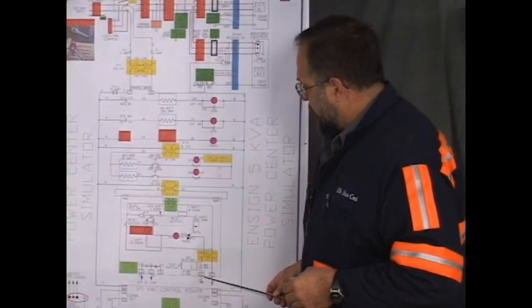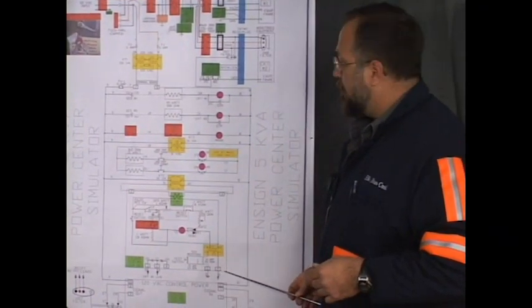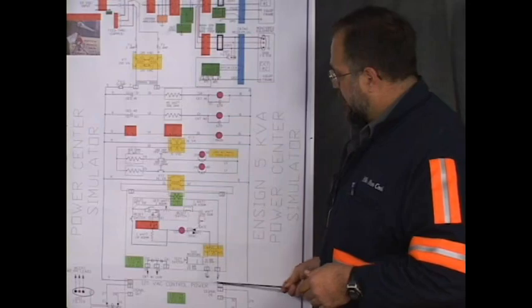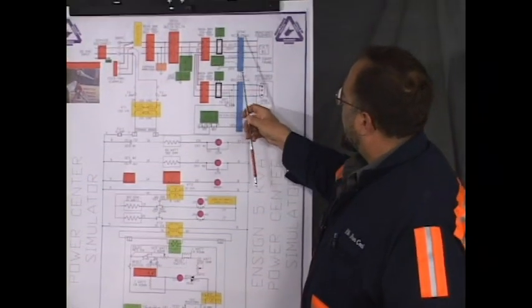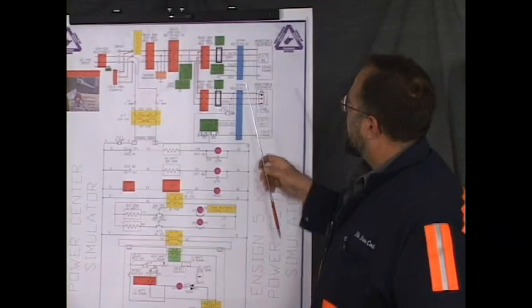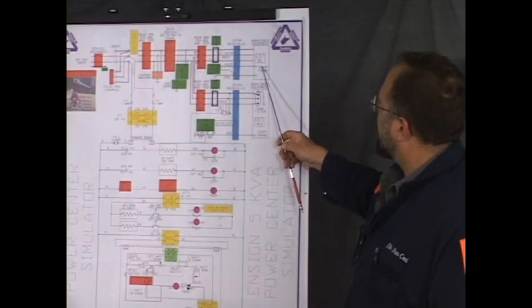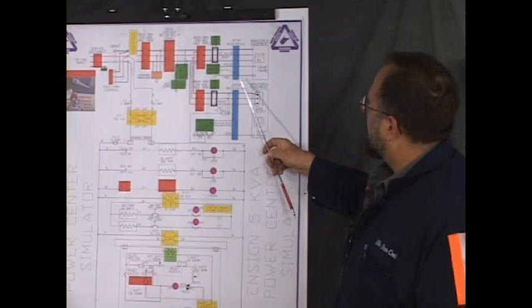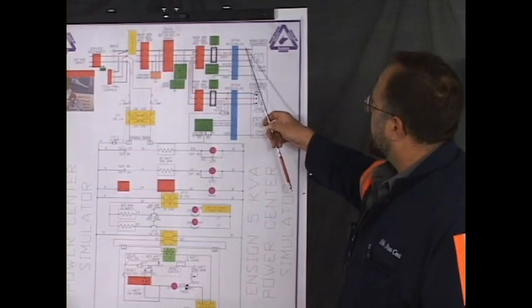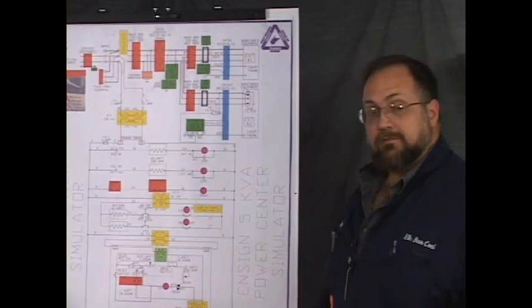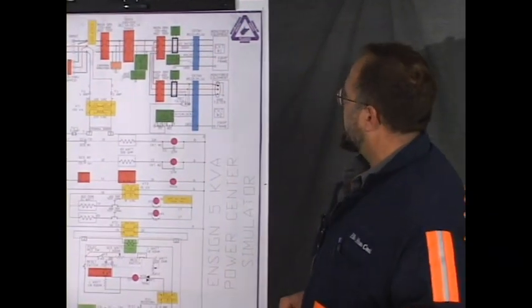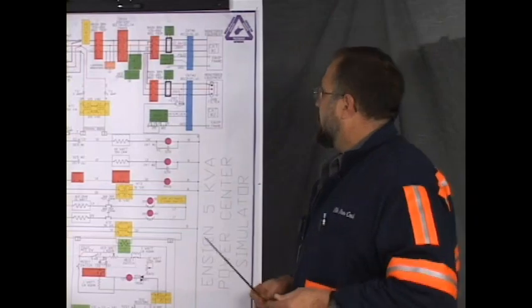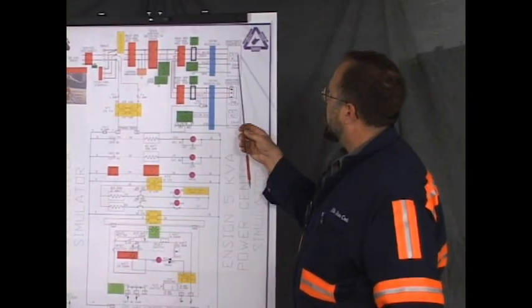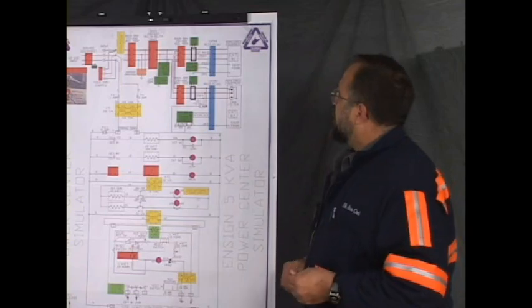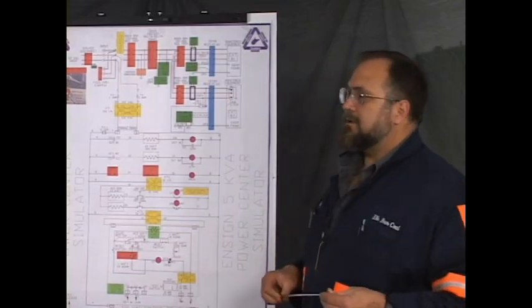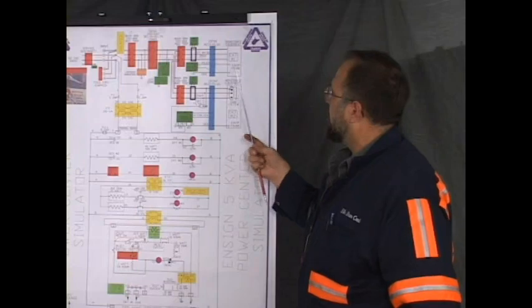This wire here goes to the ground conductor. This one here is the pilot or monitor wire. And that has to be a continuous path. It's shown here on the circuit number 1 receptacle and plug. The pilot wire goes to the equipment frame. The ground wire goes through the plug to the equipment frame. This portion here on the drawing is the cable that connects the machine to the power unit. Our machine is that box that we discussed earlier. It's symbolic of a machine. It has a main breaker in it and a grounding bus. And that will be the frame of the equipment.